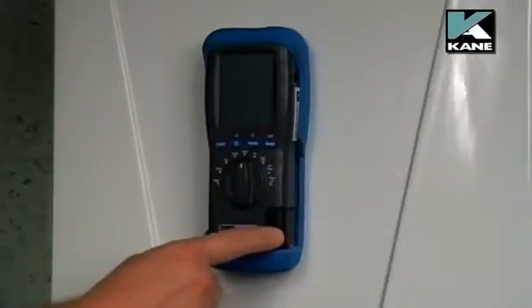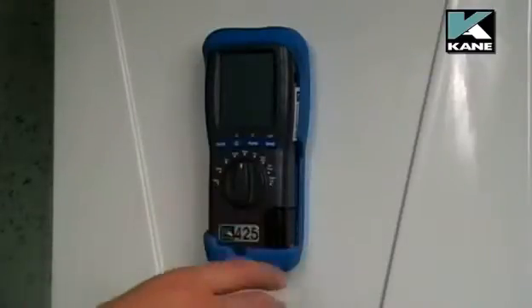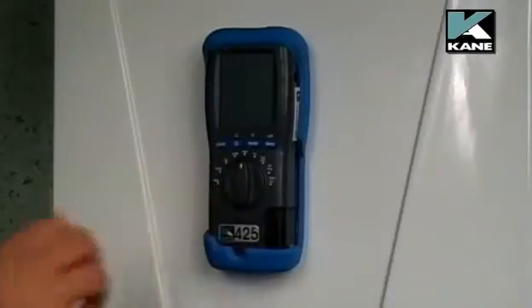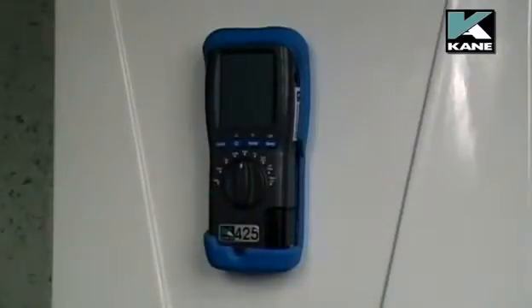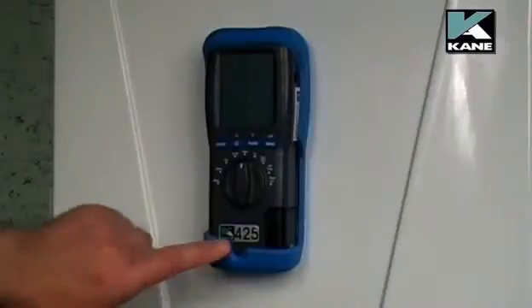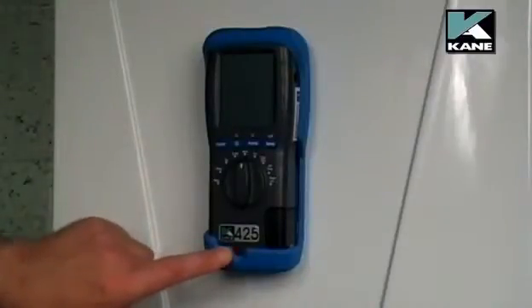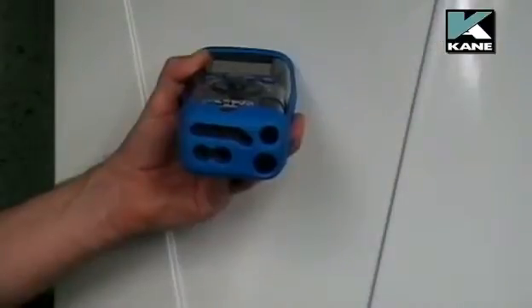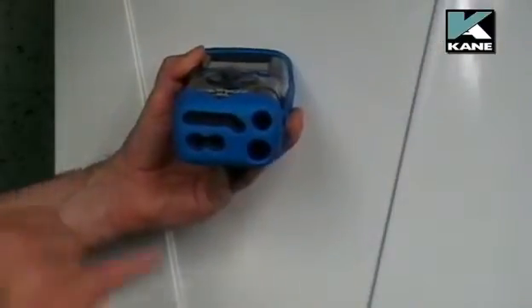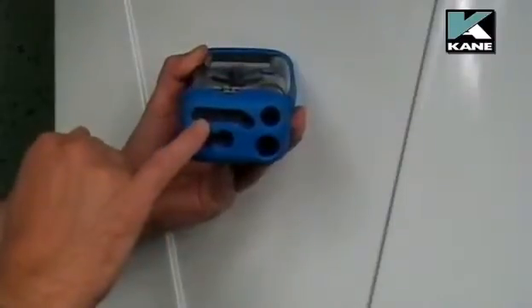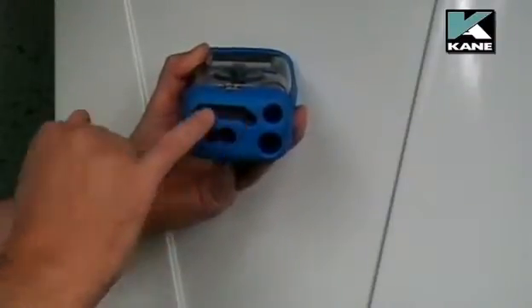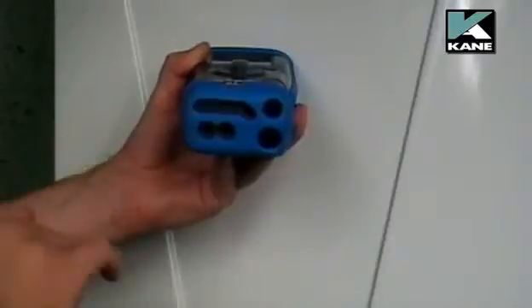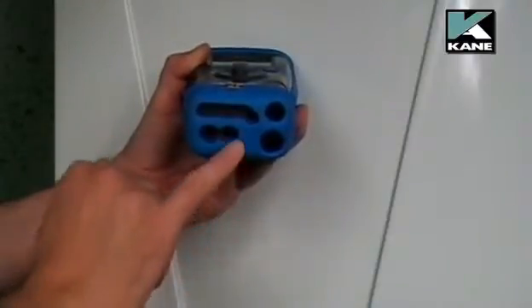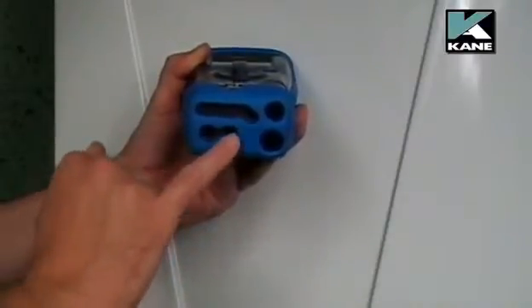Here we have the water trap, which will take out any condensate to make sure that the sample of gas going to the analyzer is a clean, dry sample. Also on the front of the analyzer is a battery charging indicator, which will be orange when it's charging. If we look at the connections on the bottom of the analyzer, you've got 2 connections for temperature. Now these are T1 and T2. You've got 2 connections for pressure, P1 and P2.